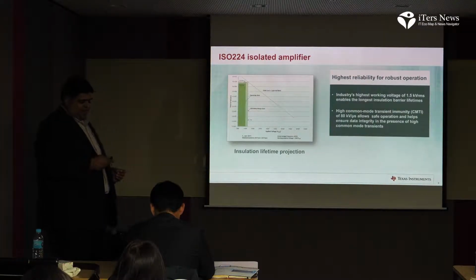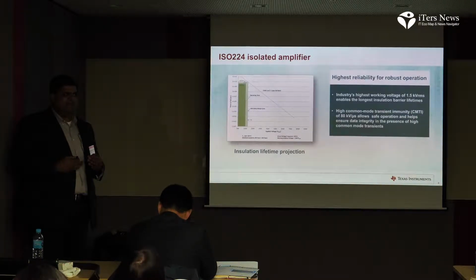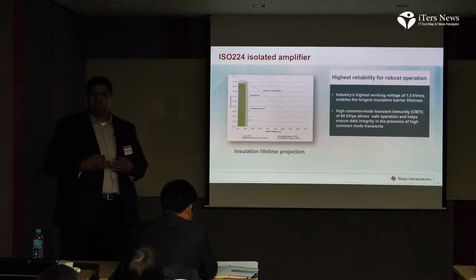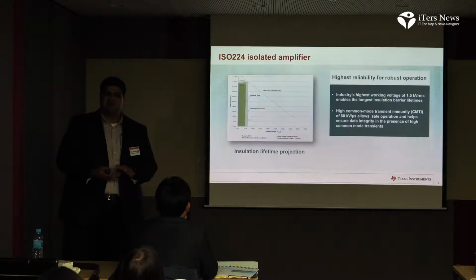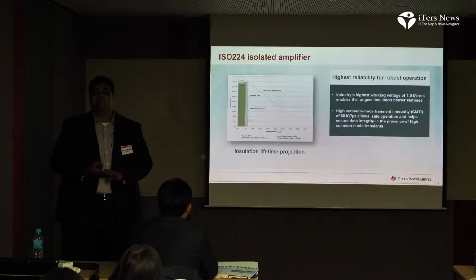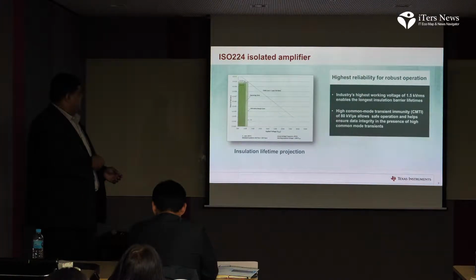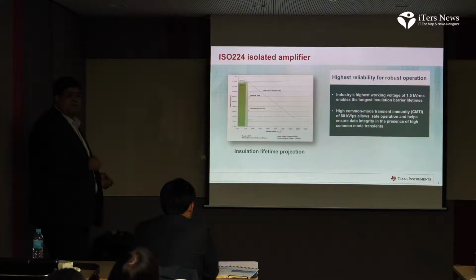To tell you how we do this testing, we use an industry standard methodology called TDDB, which stands for time-dependent dielectric breakdown. And this is the same kind of test methodology that is used for any insulative material, whether you're talking about glass, PVC, rubber, plastic, whatever it is. This is industry standard. It's been used for many decades to test what an isolation system is capable of. This is how we model a system for very long periods of time. If you look at this curve here, the y-axis is time to fail in the number of seconds.